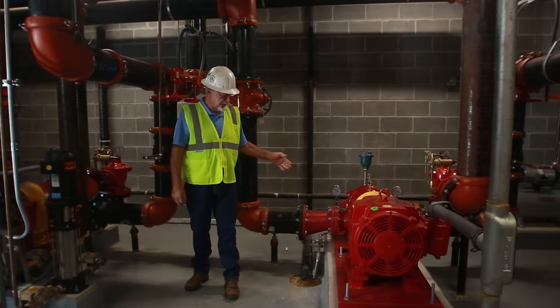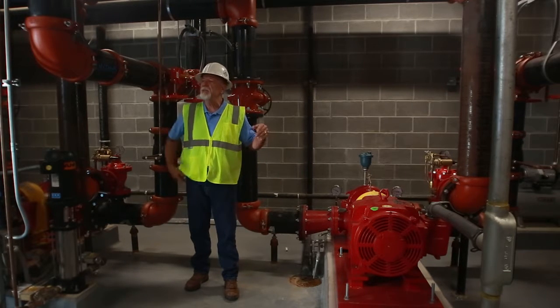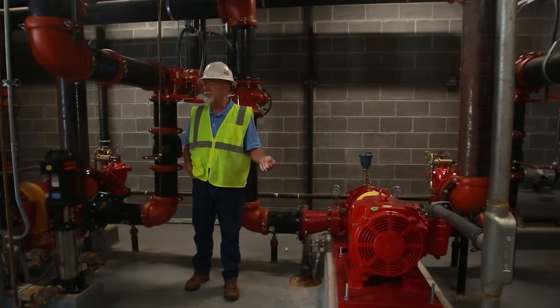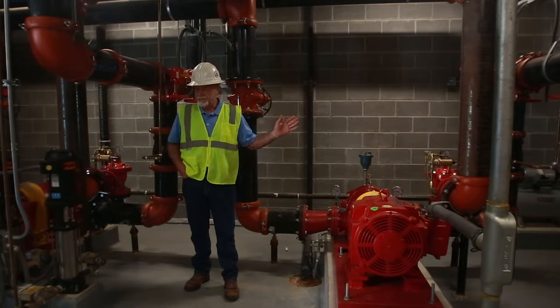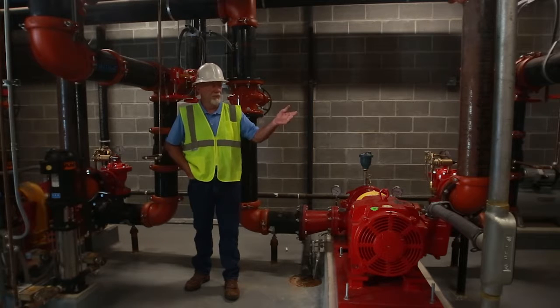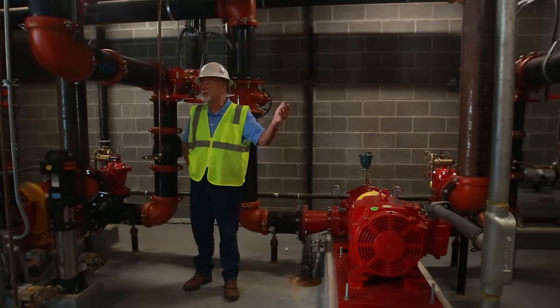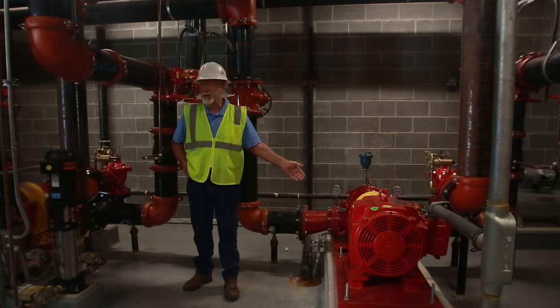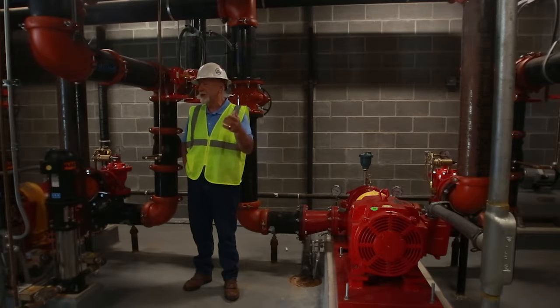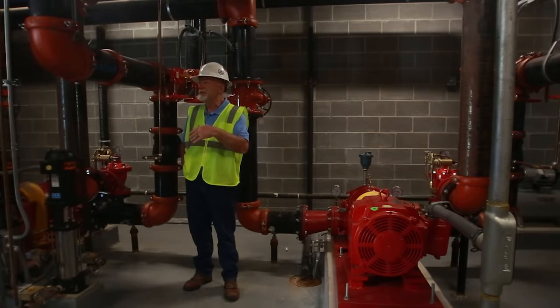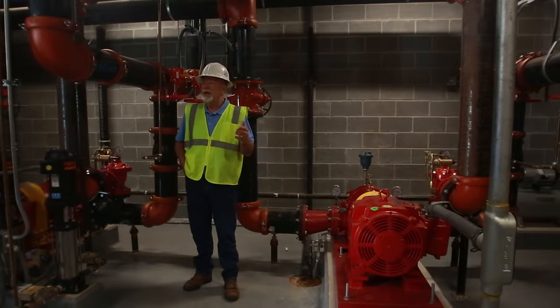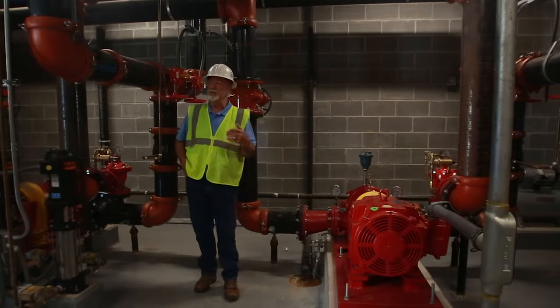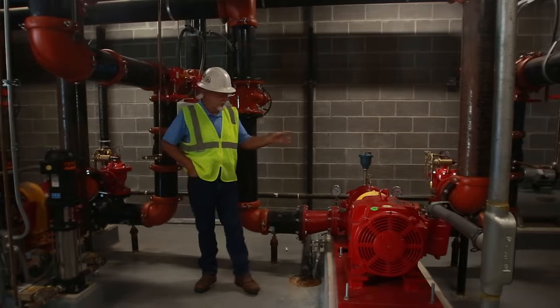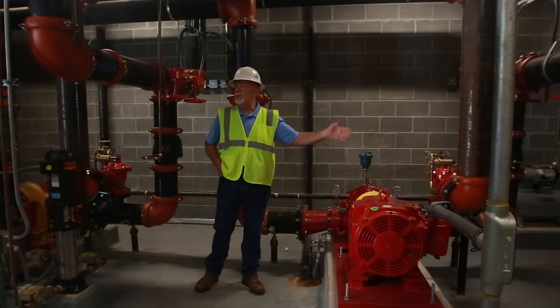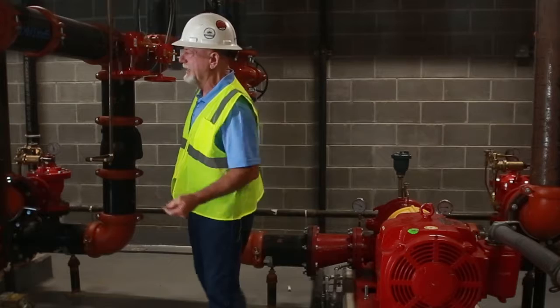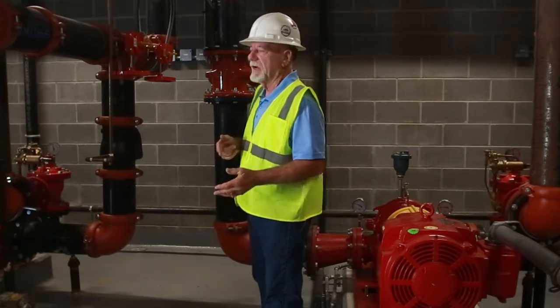What they did is they took 1,000 GPM pumps, but they added 112 pounds of head pressure to static pressure. So out here you've got 60, 70 pounds of pressure. You got 112 pounds of lift onto that, so you essentially got over 175 pounds of head pressure. When you design a system and you have that type of pressure, you've got to have a relief valve to relieve that pressure off. One of the design differences, and I don't know what that pump up there has.